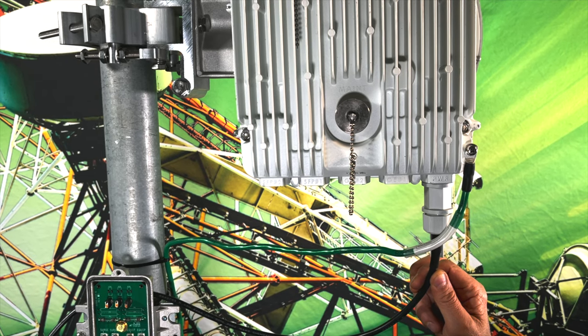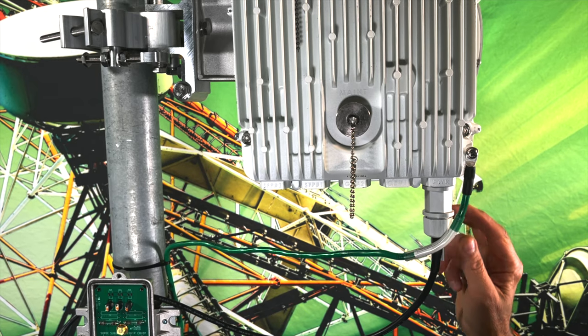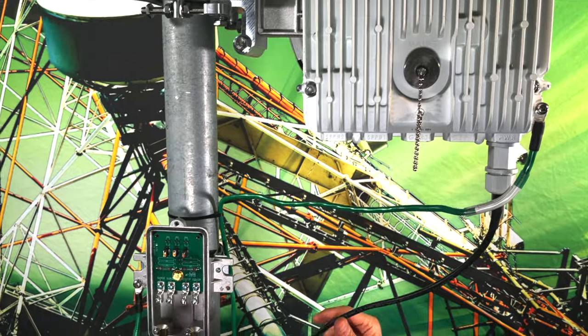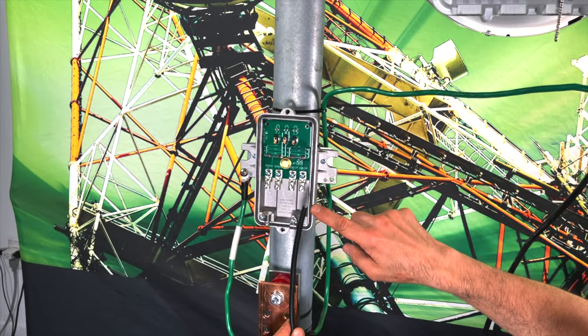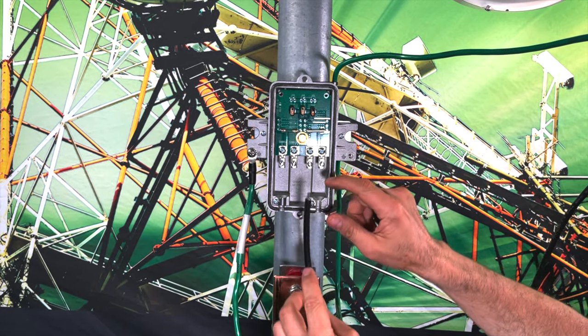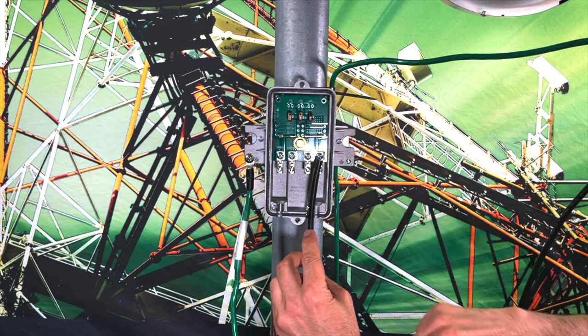Take a look at how to put the DC connector on the wire. We're going to install this on the radio, put on our weatherproof boot, and tighten it down. Now, this DC wire is going to connect into our surge arrestor. What I'm going to walk you through are the steps of how far to strip this back and how to properly terminate into the DC Defender surge arrestor.